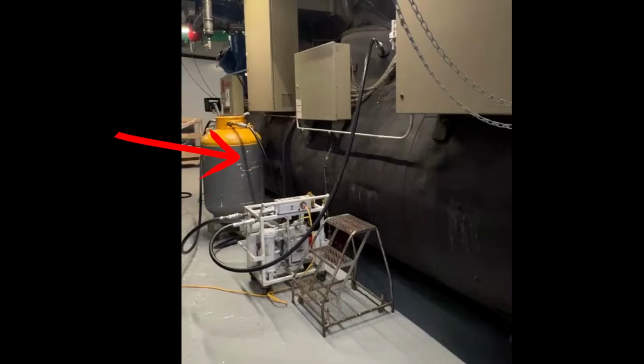We're monitoring how much refrigerant's in this cylinder and where we're at. If we have to transport it, we have to make sure that we're not going over 80%. Good rule of thumb is just not exceeding 80% in general. But again, if you have some experience and you have some understanding, you'll know what I'm talking about with the 80% rule there. Okay, if you don't, then just don't worry about it. You don't need to risk anything. It's not worth it. Just stick to the 80%. So that is the basic process. We're going to use this, and we'll change out cylinders as we need to in order to get all the refrigerant out.